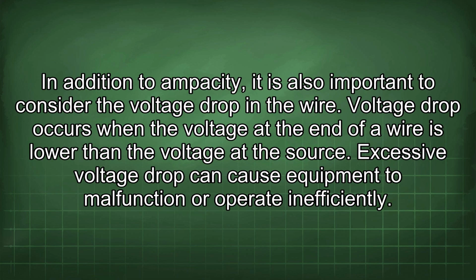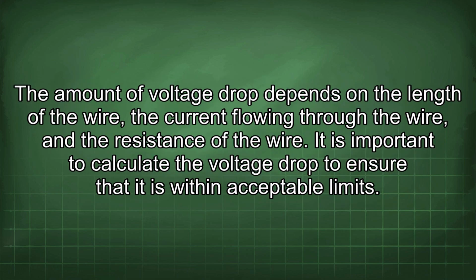In addition to ampacity, it is also important to consider the voltage drop in the wire. Voltage drop occurs when the voltage at the end of a wire is lower than the voltage at the source. Excessive voltage drop can cause equipment to malfunction or operate inefficiently. The amount of voltage drop depends on the length of the wire, the current flowing through the wire, and the resistance of the wire. It is important to calculate the voltage drop to ensure that it is within acceptable limits.